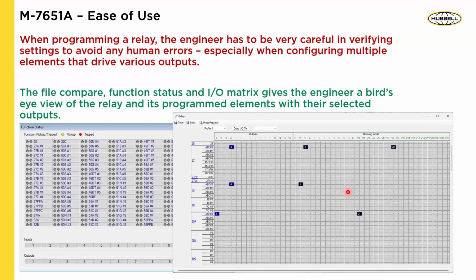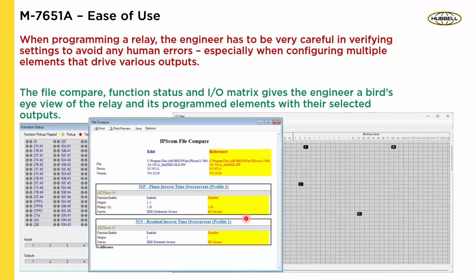And then there's an IO map, right? So if this element trips, let's say the 27 element trips, I know the output number 4 is going to go off. But if the input 3 is active, I know it's going to block it, right? So it's a very easy visual tool for you to see that there's no conflict, if you're not selecting the same blocking input for multiple elements. And then there's a file compare, obviously, so if you have a reference file and you made changes, you can easily see, because it's highlighted for you, what those changes are.